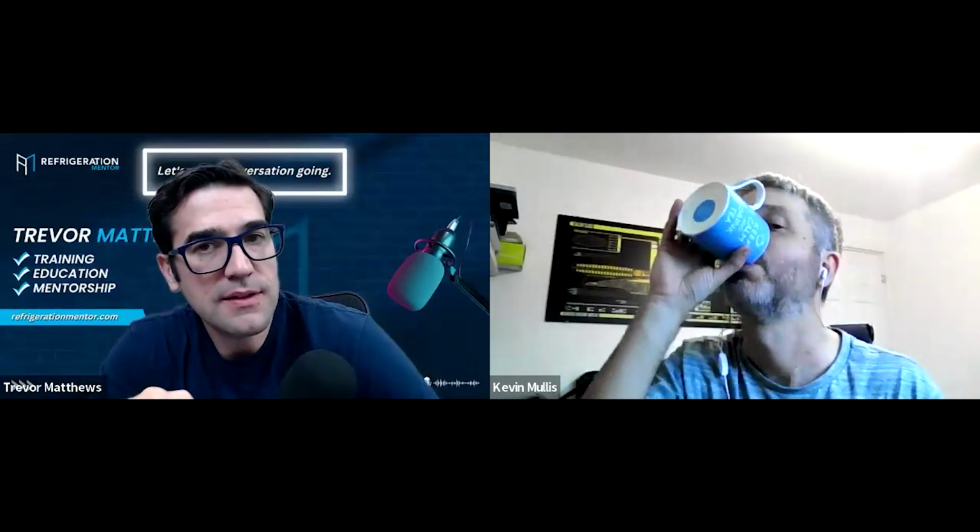And floating suction has become really popular for energy reasons. I talk to all the control manufacturers, and all their controllers can do it. The problem is it's not being done in the field, and we run into this issue, and then it's like, floating suction is no good, or it doesn't work. But Danfoss, CC200, Dixell, RDM, Wurm in Germany, all of them do it. We just need to set it up properly, and if it's not set up properly, it's not going to work.